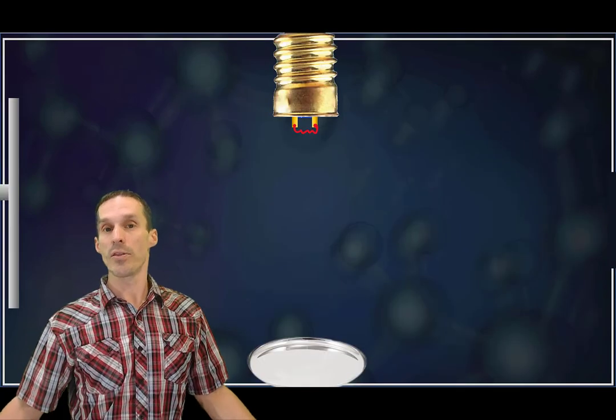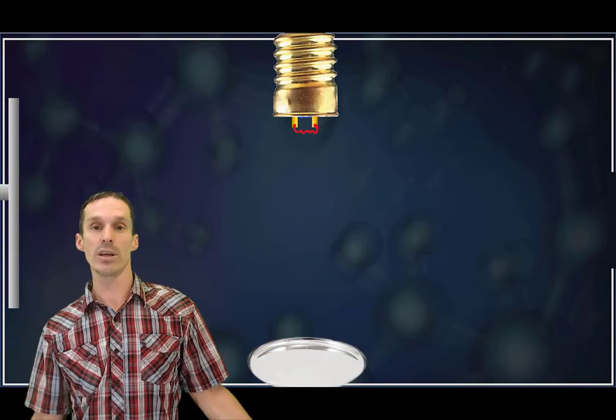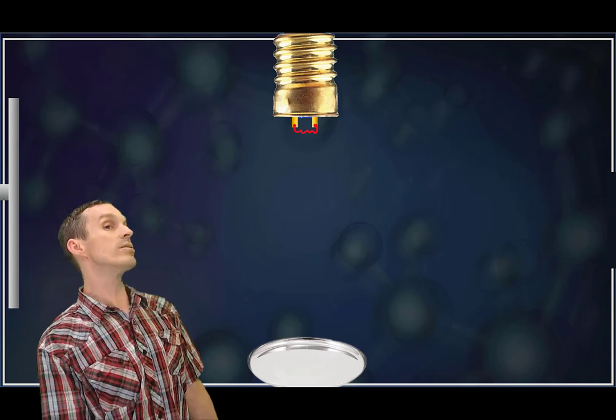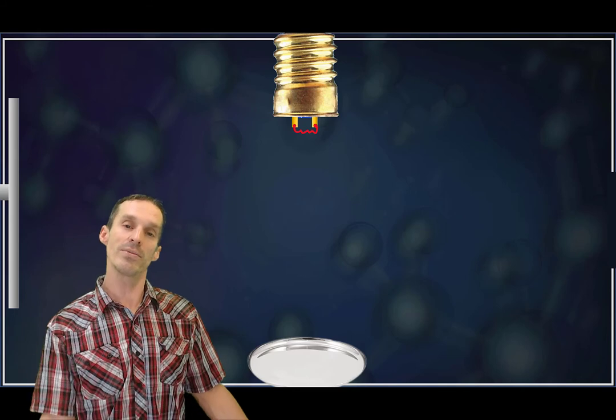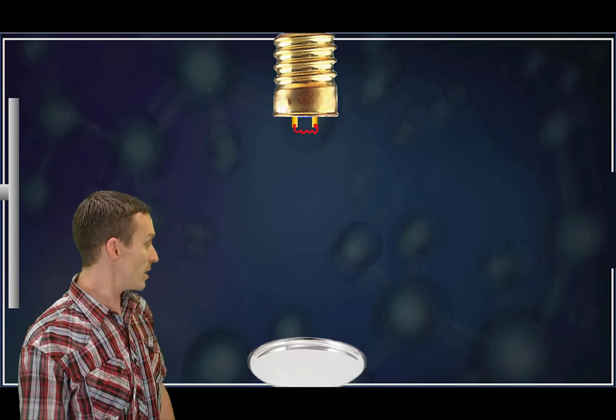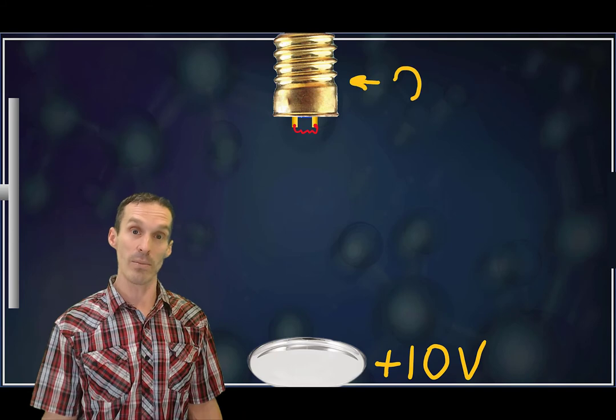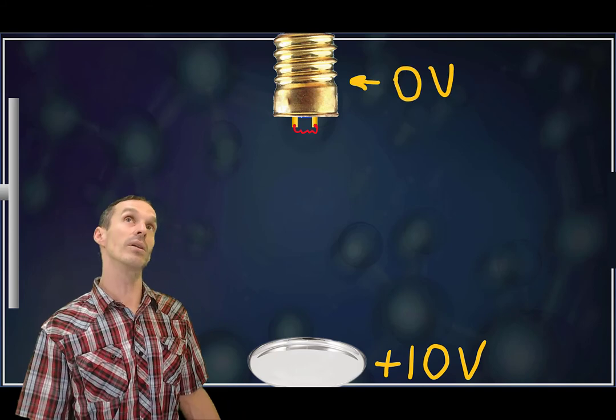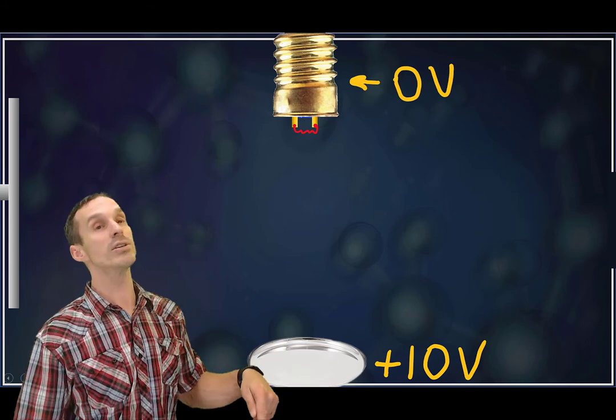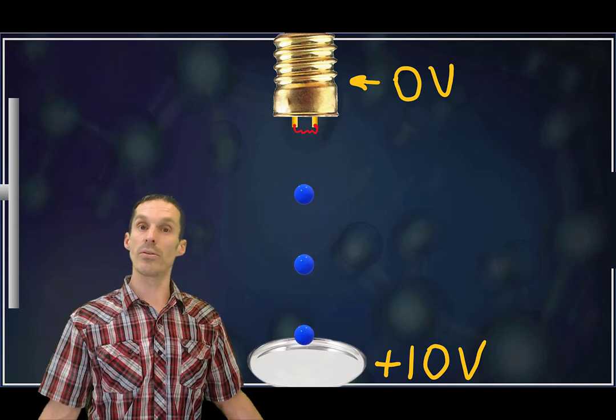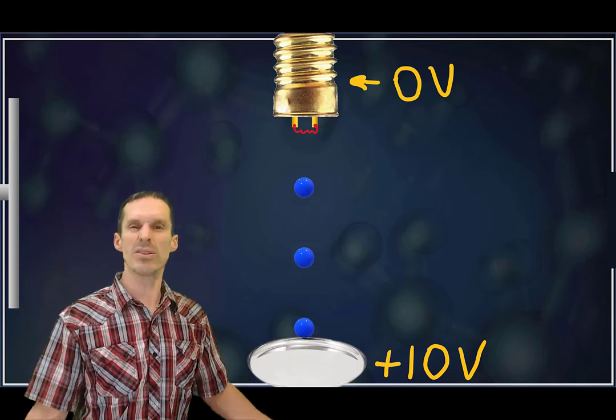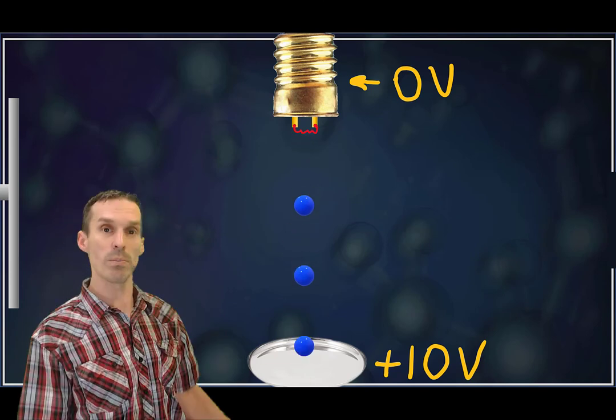Now we're inside the mass spectrometer. This is the ionization source and you can see our filament is right up there. The electrons are going to come off of that filament, but we want them to guide into a specific location. That's why we get the plate down at the bottom and we're going to apply a voltage to that. So electrons are negative, the plate is positive, so the electrons should head downhill.